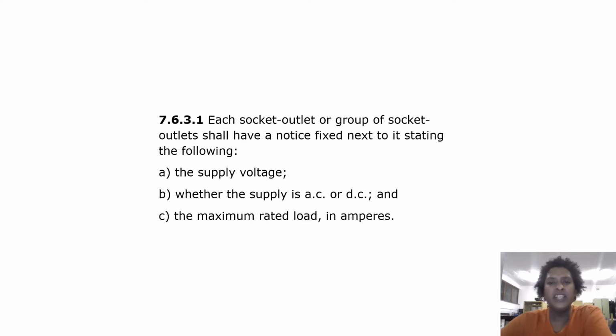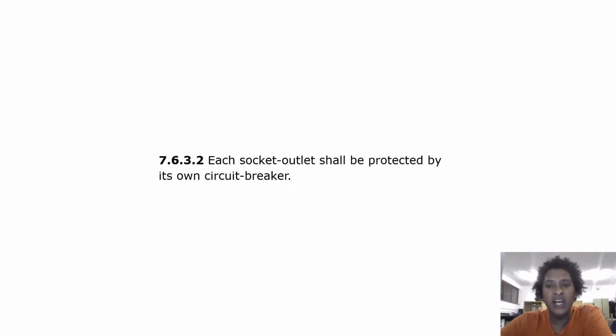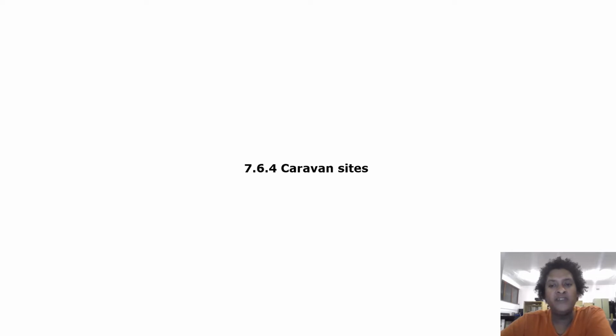Socket outlets. Each socket outlet or group of socket outlets shall have a notice fixed next to it stating the following: the supply voltage, whether supply is AC or DC, and the maximum rated load in amperes. Each socket outlet shall be protected by its own circuit breaker. Caravan sites.